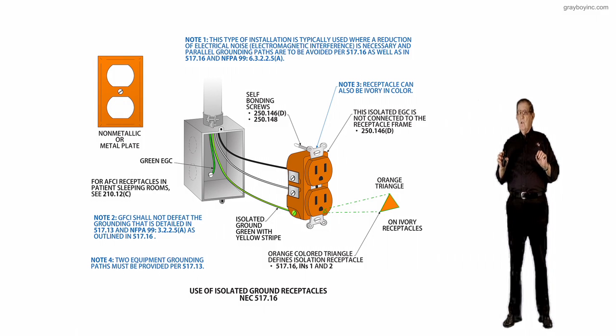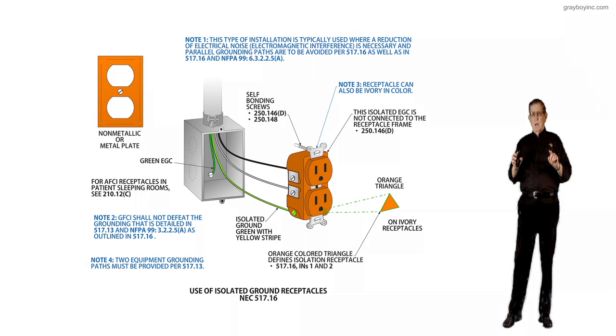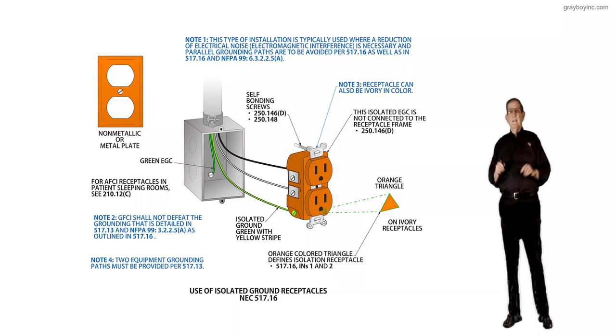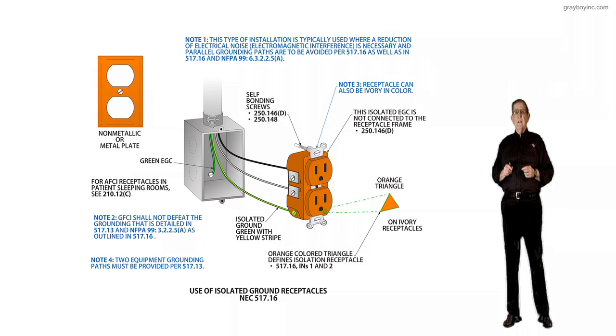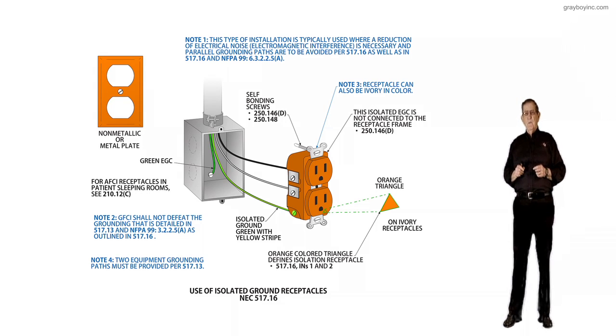Let me give you a warning by this section: these type receptacles are not permitted in your patient care areas where those receptacles are required by 517.13, 18, and 19, as you go through Article 517 to review these sections.